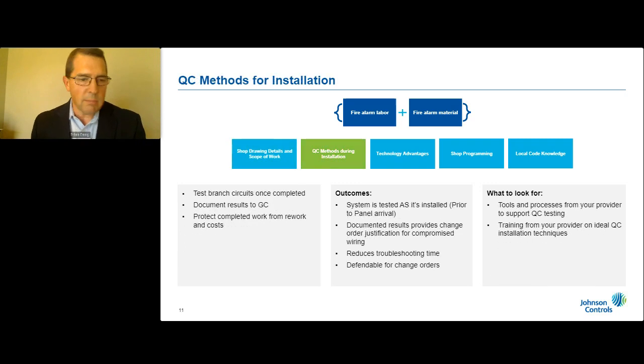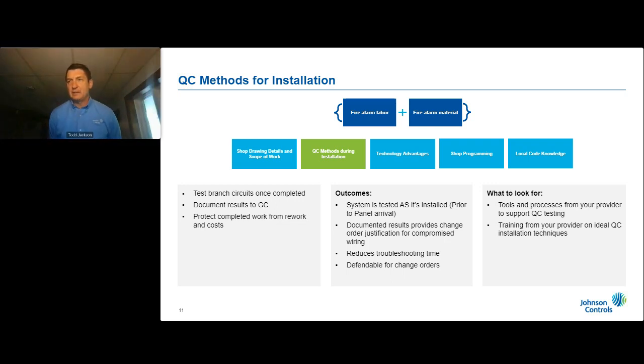Next up is quality control. So QC methods for installation - there are some fire alarm providers that can really get you ahead of the curve on this. Best practices we see are installers testing branch circuits once they're completed, ideally before the fire alarm panel shows up, because oftentimes you have to wait for power to be run to that panel to make it useful. You don't want to use that high-dollar piece of equipment as a piece of test equipment out of the chute when you get your infrastructure and wiring plant in place. The best providers offer ways to test these branch circuits and validate them - and when I say test, I mean beyond just a simple multimeter check for a short to ground, or whether you have the right resistance loop down the wire through the end-of-line resistor and back.